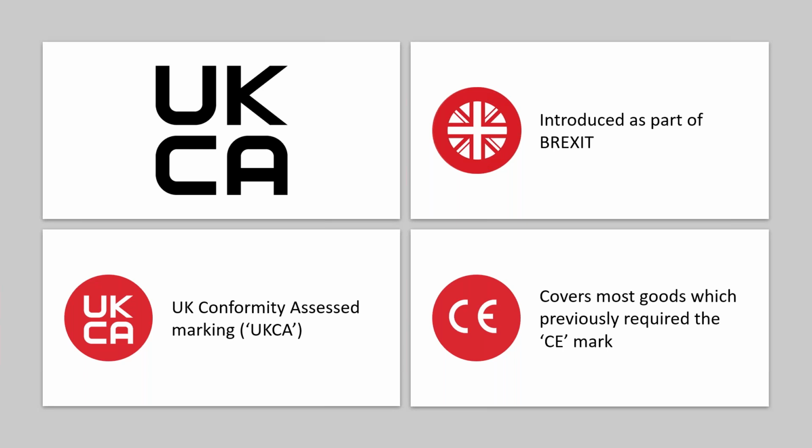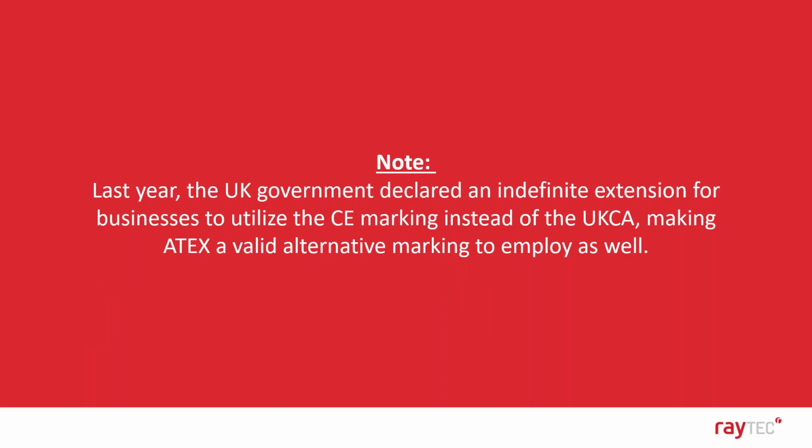Now, I said "was" in that part of the webinar because last year the UK government declared an indefinite extension for businesses to utilise the CE mark and continued recognition of the CE mark within the UK. So essentially that makes the ATEX directive and certification a valid alternative marking to employ as well going forward.